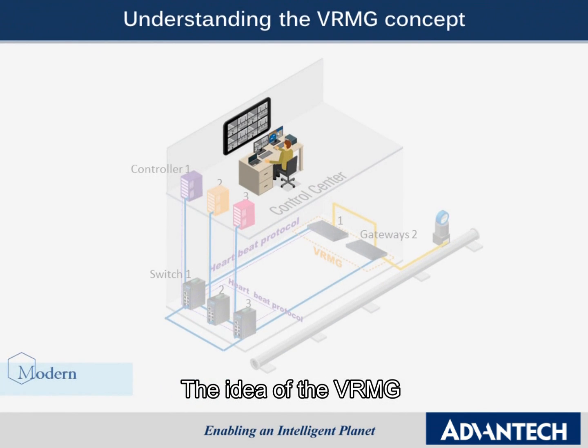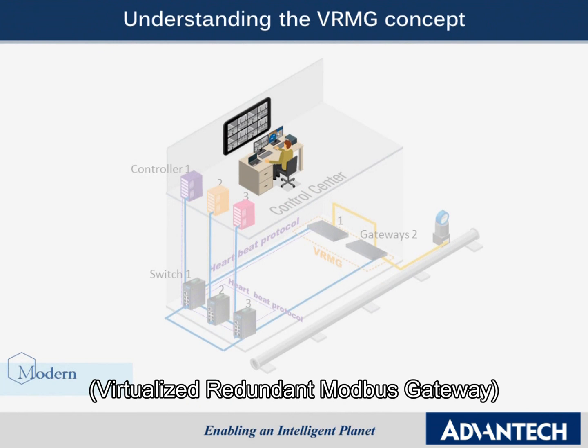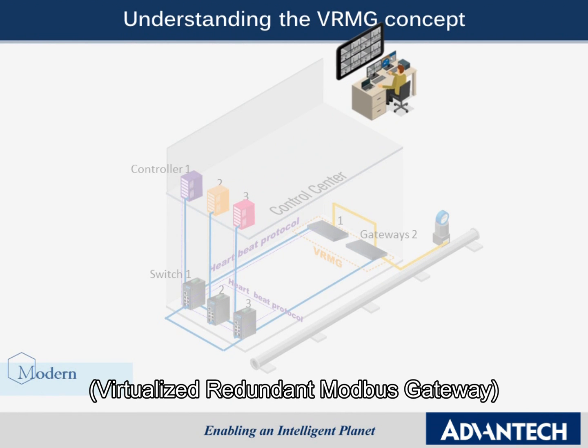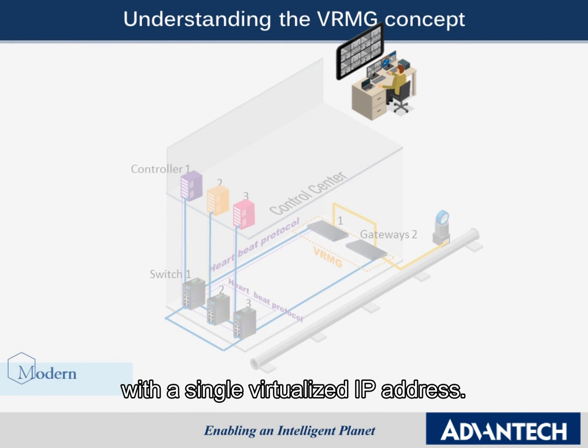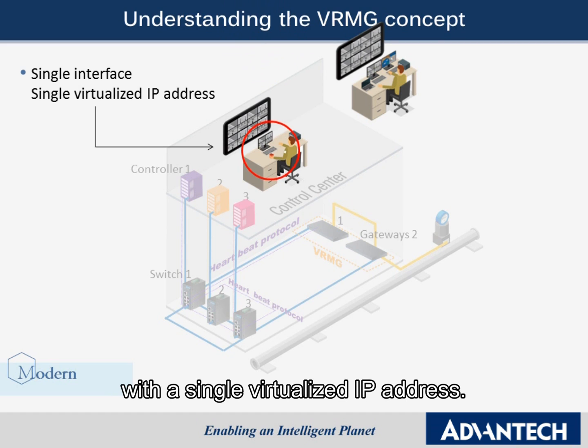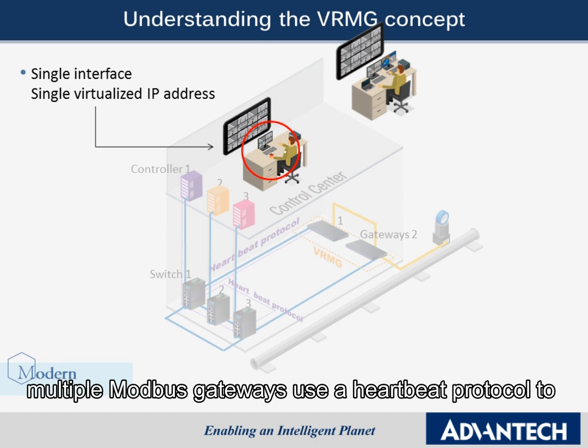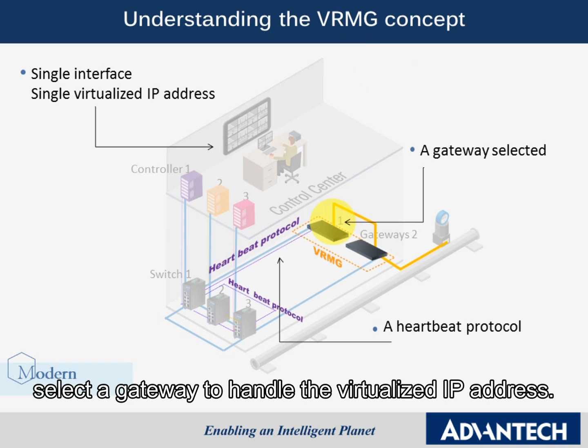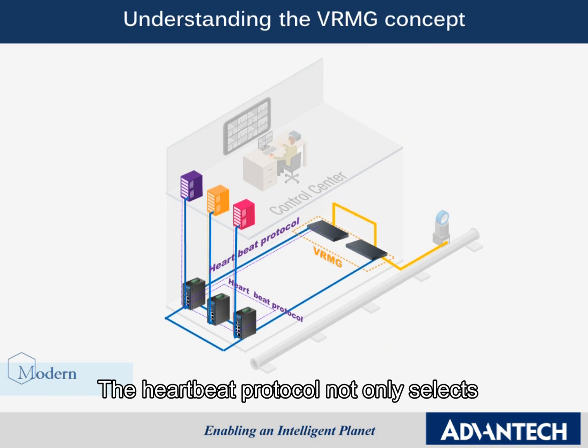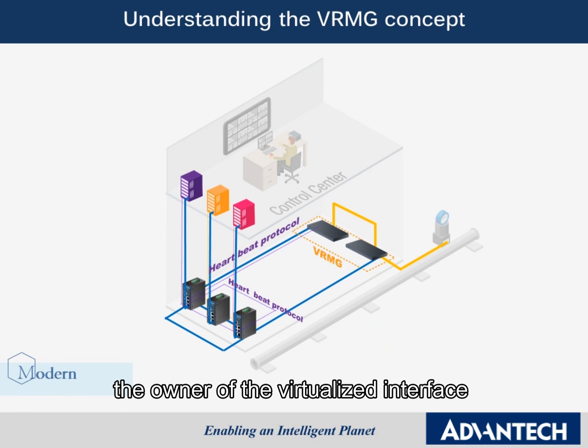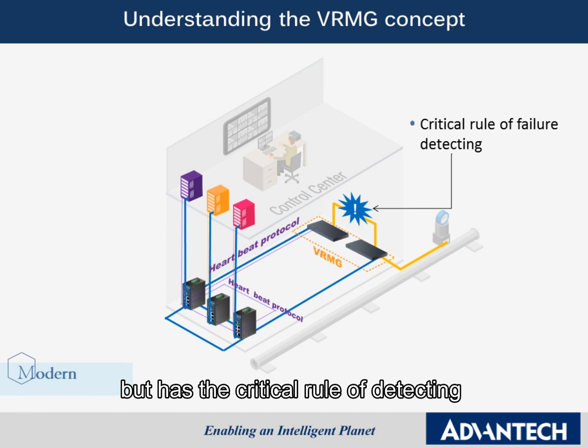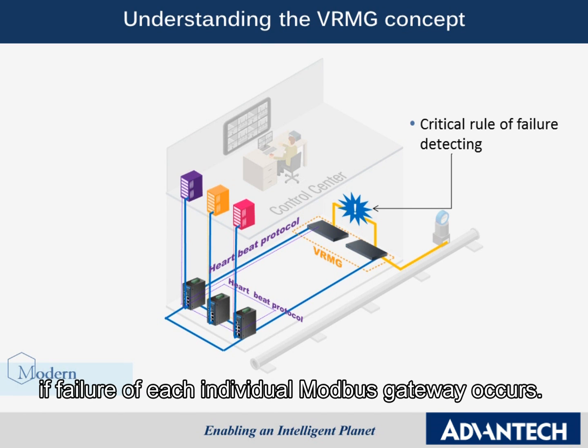The idea of the VRMG — virtualized redundant Modbus gateway — is to create a virtualized Modbus gateway with a single virtualized IP address. In the background, multiple MOBA's gateways use a heartbeat protocol to select a gateway to handle the virtualized IP address. The heartbeat protocol not only selects the owner of the virtualized interface but has the critical role of detecting if failure of each individual Modbus gateway occurs.